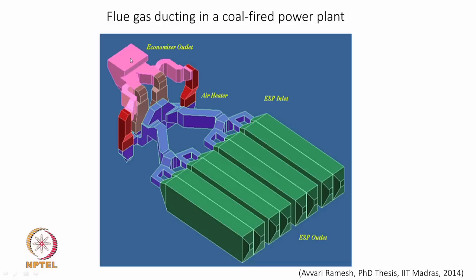This hot gas is sent into two heat exchangers — shown in red and brown — which are air preheaters. The hot flue gas heats up the incoming combustion air, exchanging thermal energy that would otherwise be lost. To make this happen, the flow coming through a rectangular vertical duct takes a 90-degree turn and splits into two streams: one going left and one going right. This stream is then further split into one going through a primary air heater and one through a secondary air heater.